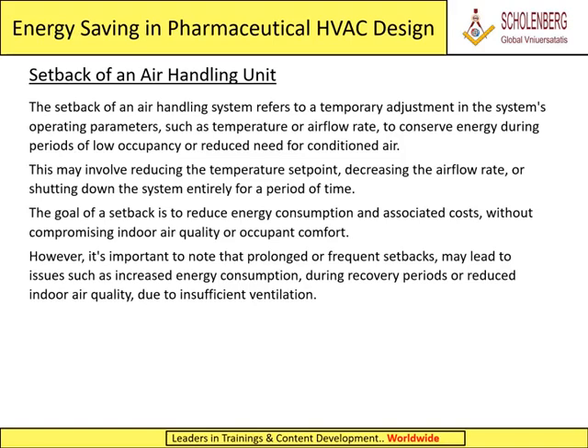This may involve reducing the temperature set point, decreasing the airflow rate, or shutting down the system entirely for a period of time. The goal of a setback is to reduce energy consumption and associated costs, without compromising indoor air quality or occupant comfort. However, it's important to note that prolonged or frequent setbacks may lead to issues such as increased energy consumption during recovery periods or reduced indoor air quality due to insufficient ventilation.